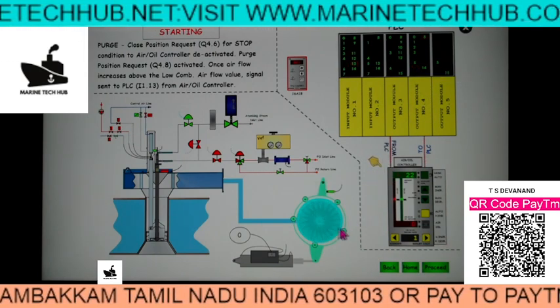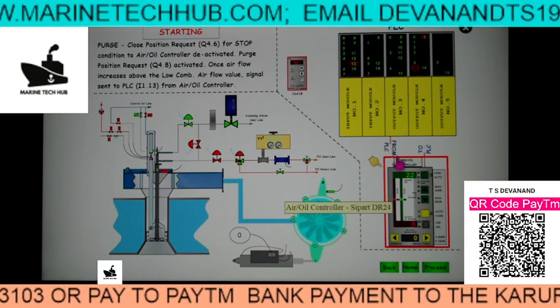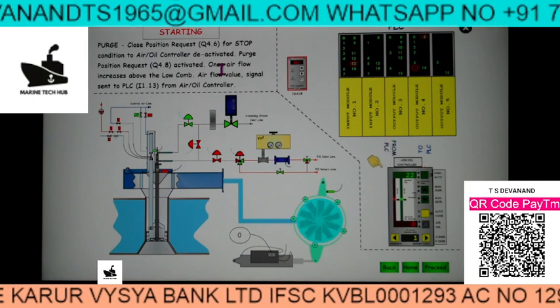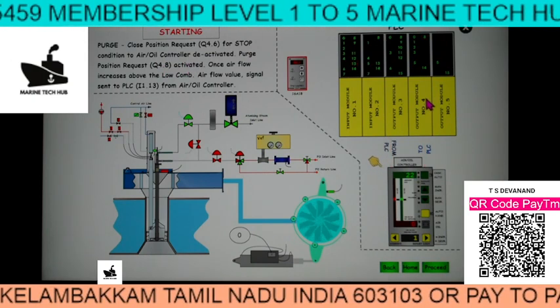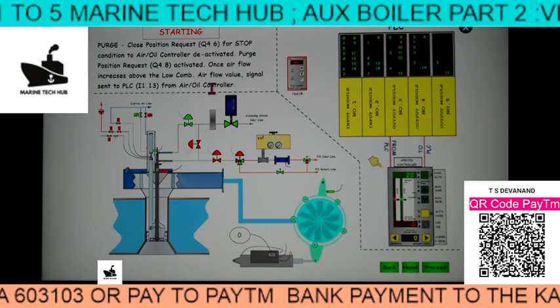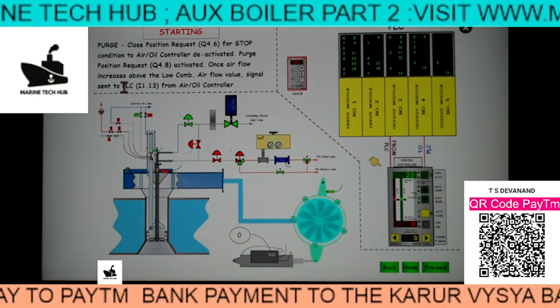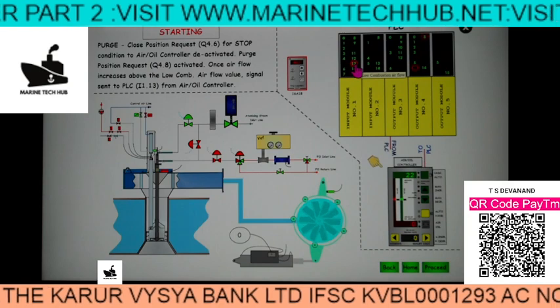Purge position request 4.8 is activated — module 4, position 8 is the purge position request activated. Air flow value signal is sent to PLC 1.13 — module 1, position 13 — 'low combustion air flow.' Now the purging is at 70%. You can see the FD fan vane opening up, so air is going until you reach 70% air flow. This is the purging operation. Purge means air flow 70% and oil flow 20%. The air oil controller sends signals to the FD fan vane positioner; the vane opens until air flow reaches 70%.